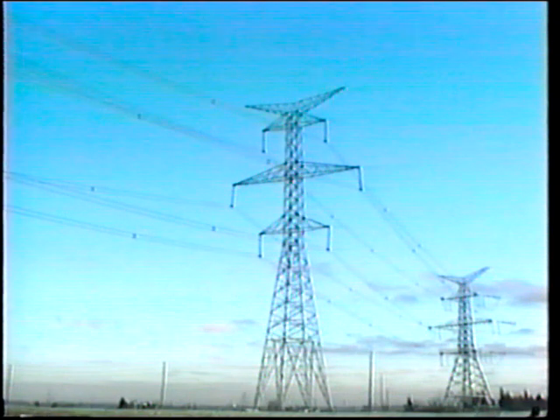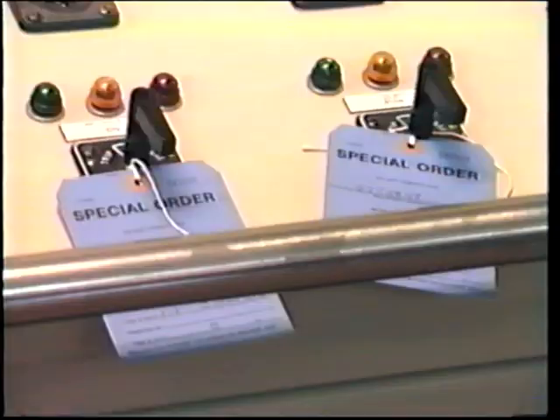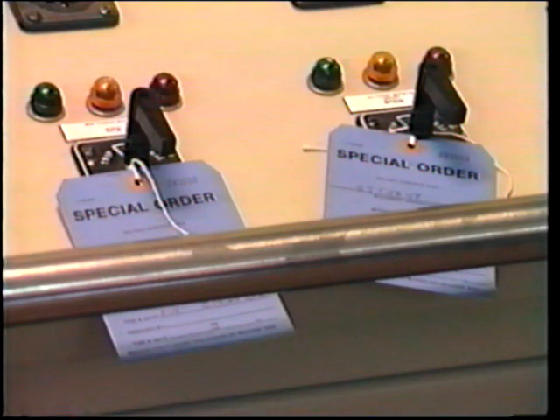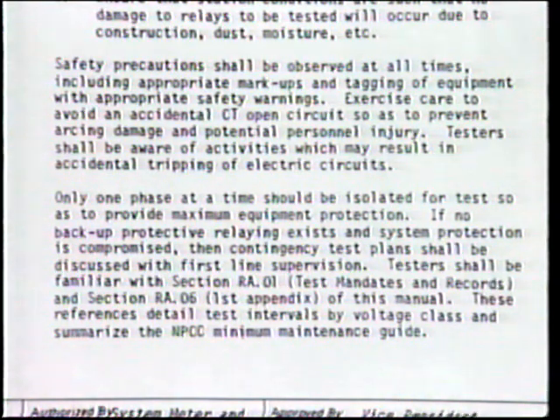With certain items of equipment, it may not be possible to arrange an outage, and in this case, the routine testing of protection schemes will have to be carried out on live equipment. The subject of in-service tests will be discussed in detail in the following segment. So let us consider that our tester has received a work permit and the circuit under test is isolated at his disposal. What tests will he perform? Well, your company will have very detailed procedures laid out for testing all of the different types of relays and protection schemes on your system. You must have access to these procedures and use them when performing any tests. In general, the procedures cover the following areas.